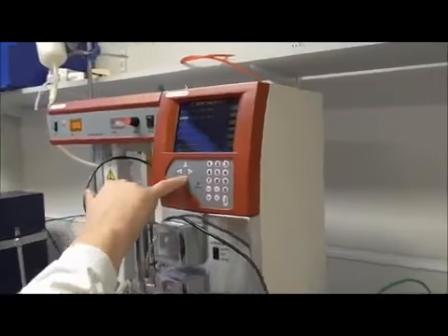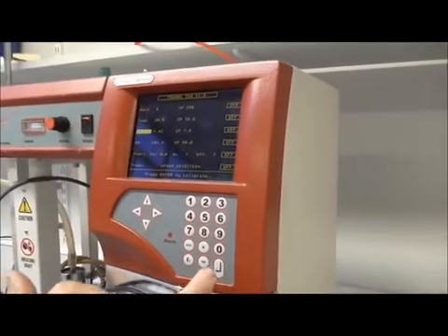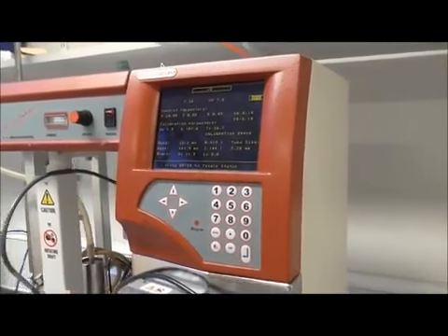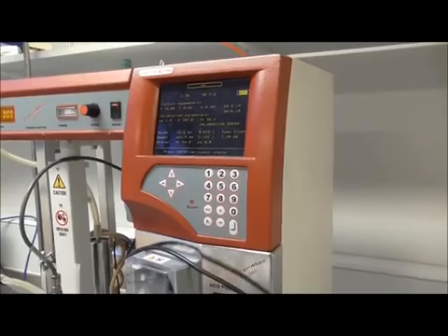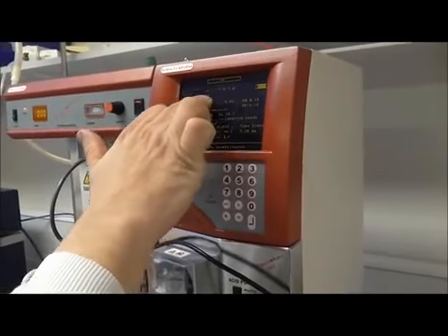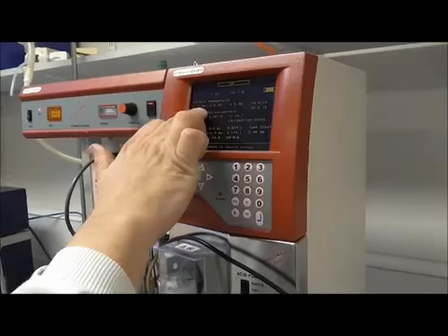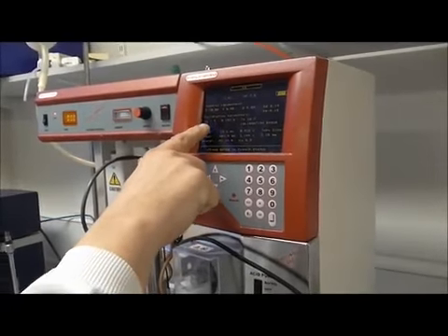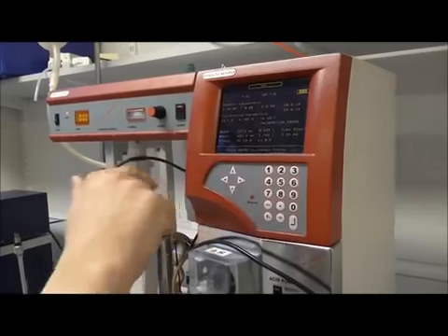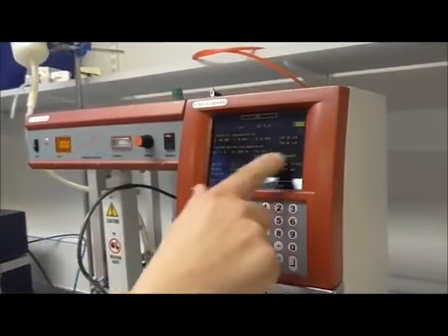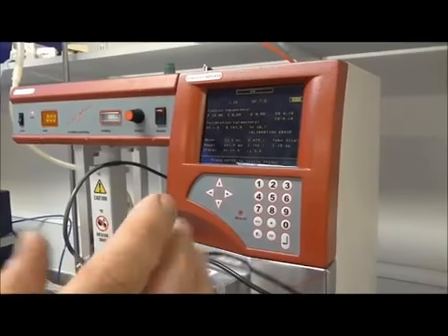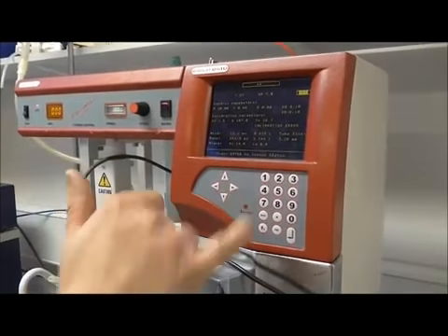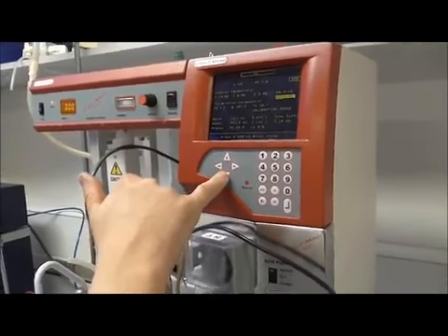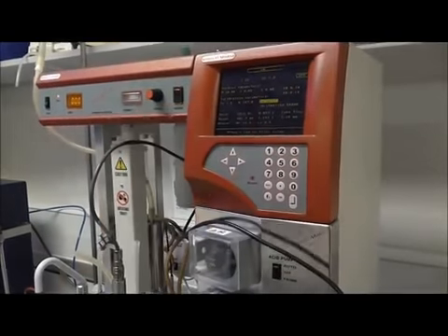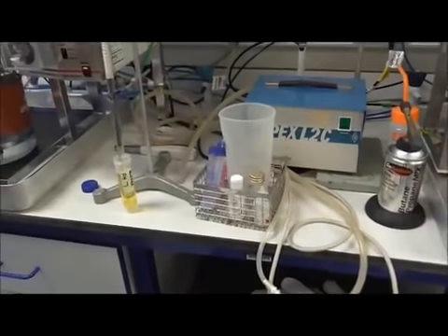On the main menu, we scroll the cursor block where it's sitting over pH, we press enter and we enter the calibration menu. Across the top is our set point, there is our actual reading, we have our PID terms across here, in the middle are our calibration parameters 0 and gain and temperature. It is indicating calibration error at the moment. Again, do not be alarmed. The first thing we need to do is tell the controller the temperature of the buffer.